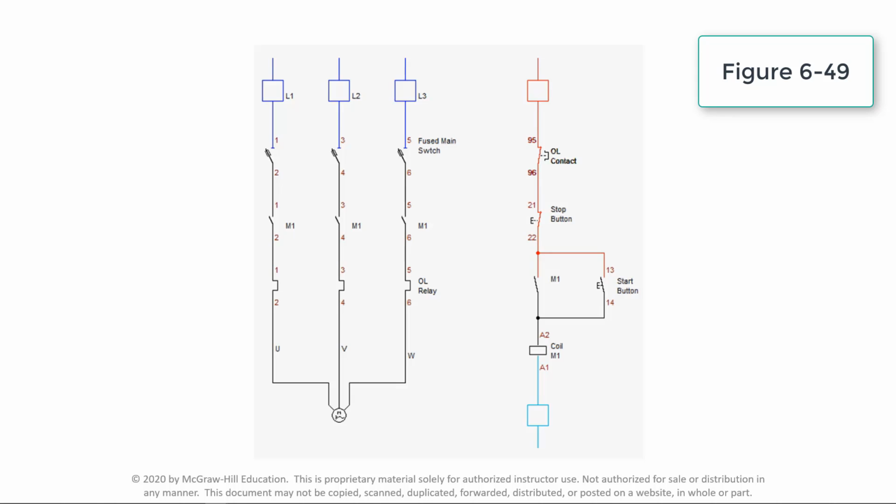The numbers 1-3 and 1-4 represent an auxiliary contact. The number 1 identifies that this is the first contact in the sequence. The numbers 3 and 4 identify this as a normally open contact. The numbers 2-1 and 2-2 represent another auxiliary contact. The number 2 identifies that this is the second contact in the sequence. The numbers 1 and 2 identify this as a normally closed contact.